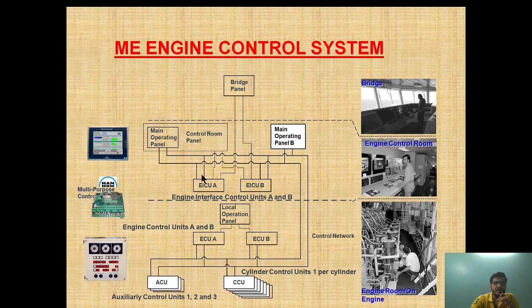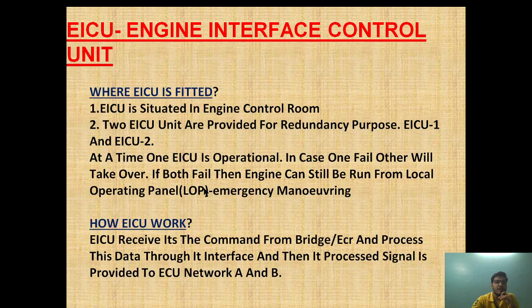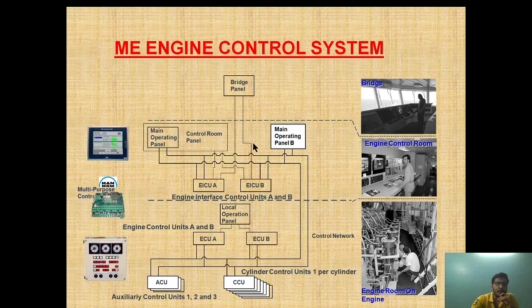Let's discuss EICU first. EICU is situated in the engine control room. Two EICU units are provided for redundancy purposes — EICU 1 and EICU 2. The command from the bridge panel passes through the main operating panel and comes to EICU A or EICU B. Two units are provided so that if one fails, the other takes over and engine performance is not hampered.